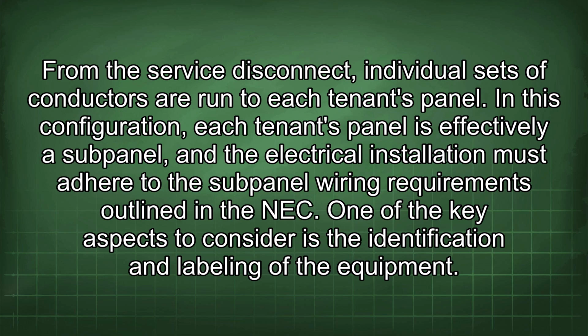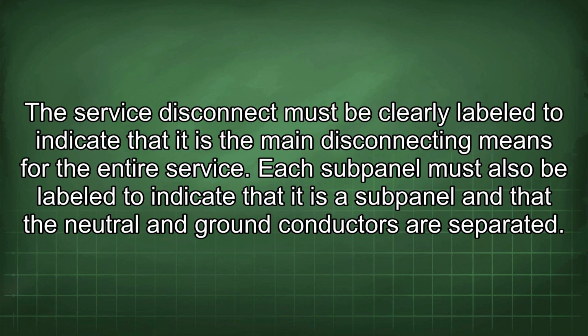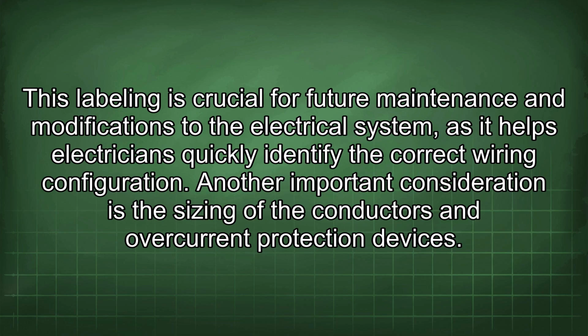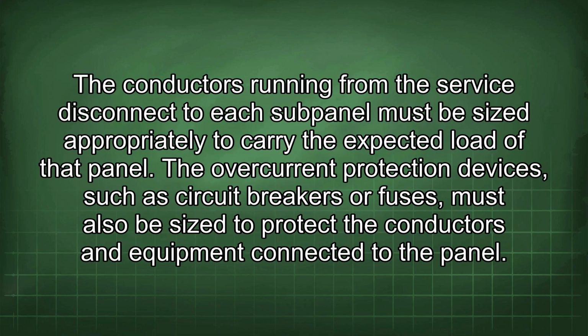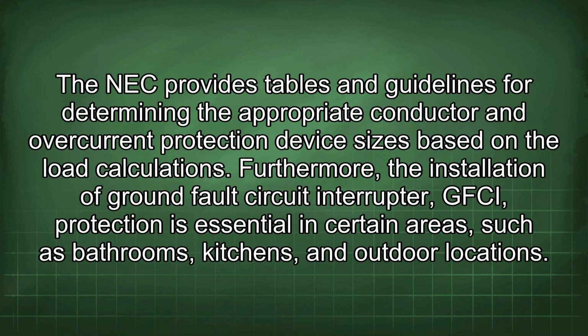One of the key aspects to consider is the identification and labeling of the equipment. The service disconnect must be clearly labeled to indicate that it is the main disconnecting means for the entire service. Each subpanel must also be labeled to indicate that it is a subpanel and that the neutral and ground conductors are separated. This labeling is crucial for future maintenance and modifications to the electrical system, as it helps electricians quickly identify the correct wiring configuration. Another important consideration is the sizing of the conductors and overcurrent protection devices. The conductors running from a service disconnect to each subpanel must be sized appropriately to carry the expected load of that panel. The overcurrent protection devices, such as circuit breakers or fuses, must also be sized to protect the conductors and equipment connected to the panel.